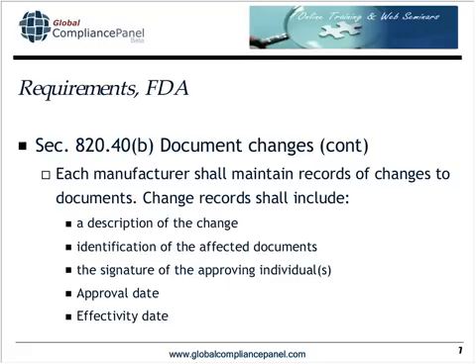Identification of the affected documents. There are going to be changes that impact more than one document, and it's your ECO or ECN where you need to make sure to include all the affected documents that were changed. Do not forget your Tier 1 index document. What that is, it's a list of all of your quality system documents that you use. Each time you change one of those, your index is going to change also.